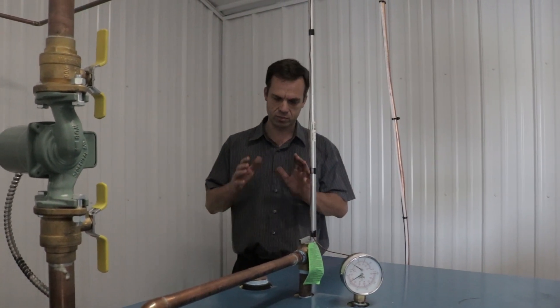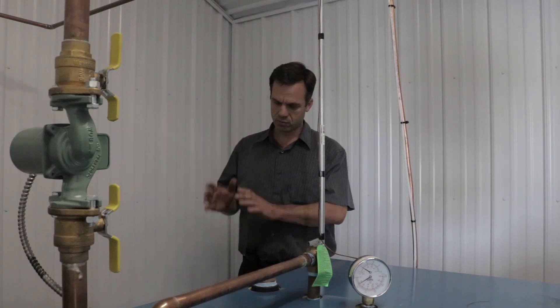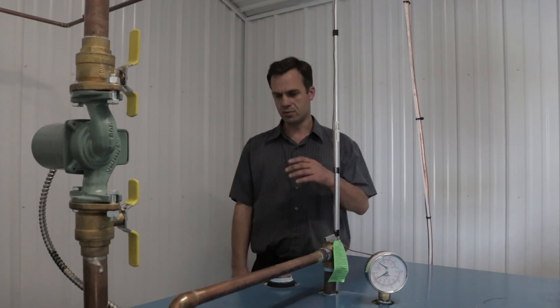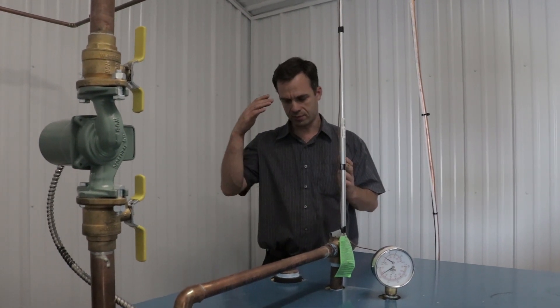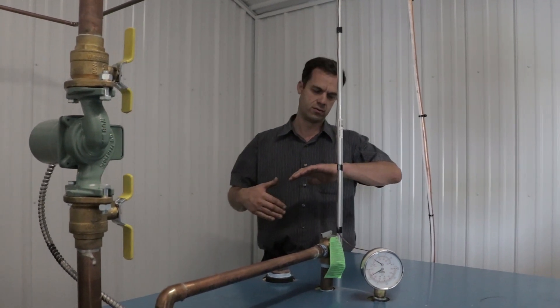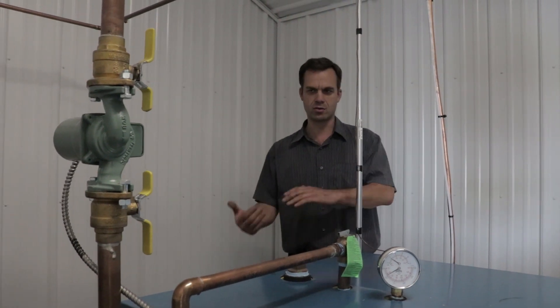So if your boiler is in your shop in a room that has an exhaust fan, you must have a louver, and the exhaust fan must have an interlock switch, so that the fan cannot run unless the louver is wide open.